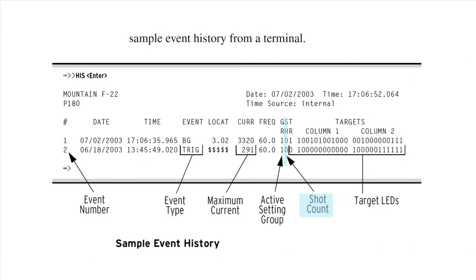Shot count. When three-phase reclosing is enabled, the SEL651R reports the recloser control shot count present at the start of the event report. When single-phase reclosing is enabled, the SEL651R reports the highest recloser control shot count present at the start of the event report. When the recloser control is defeated, the shot count field will contain a blank.